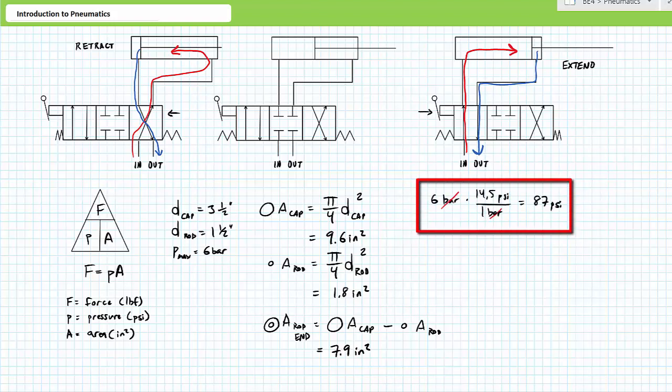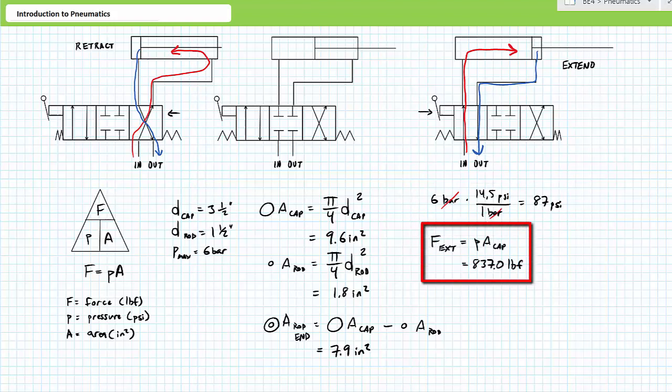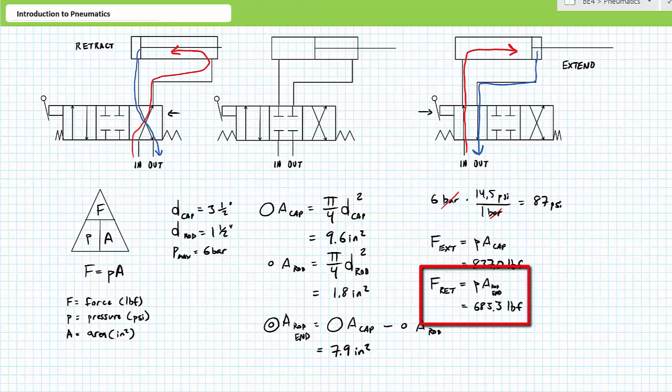One bar is equal to roughly 14.5 psi. A unit conversion demonstrates our maximum pressure of 6 bar is equal to roughly 87 psi. Extension uses the full circular cap end area. An application of Pascal's law demonstrates that 87 psi acting on the surface area of 9.6 square inches results in a maximum extension force of roughly 837 pounds. Retraction uses the smaller ring-like rod end area. An application of Pascal's law demonstrates 87 psi acting on a surface area of 7.9 square inches results in a maximum retraction force of roughly 685.3 pounds force. You will note that given the same pressure, extension force is greater than retraction.